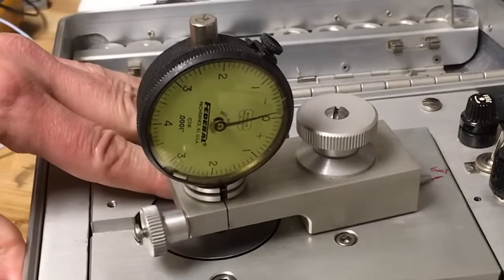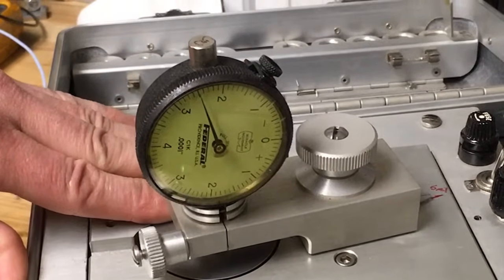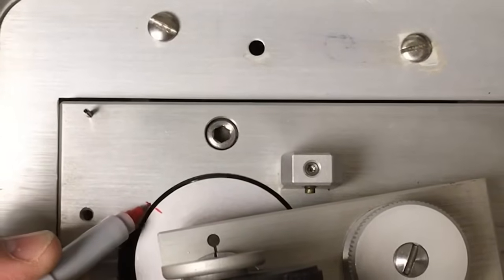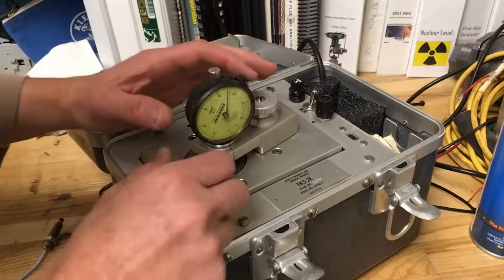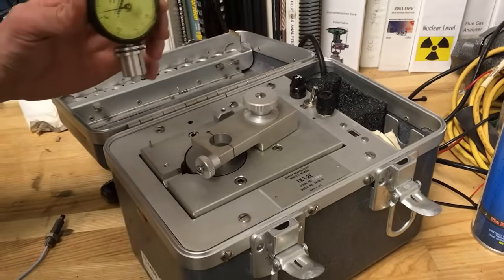Rotate the disc to the midpoint of the travel, which should be two point five thousandths of an inch. Place a reference mark on the disc for future use. Loosen the locking screw, then remove the dial assembly, being careful not to move the swing arm.